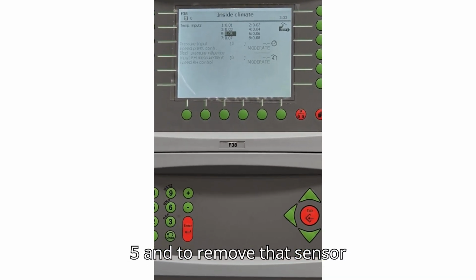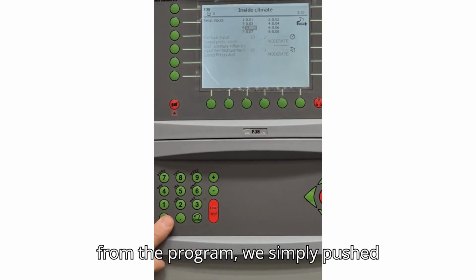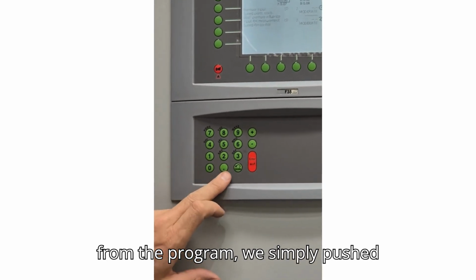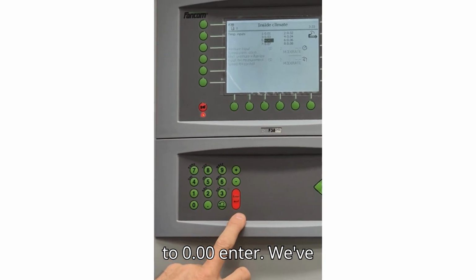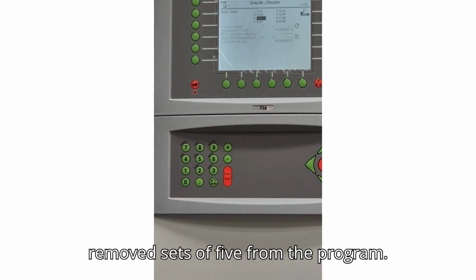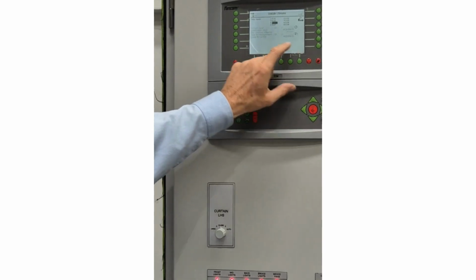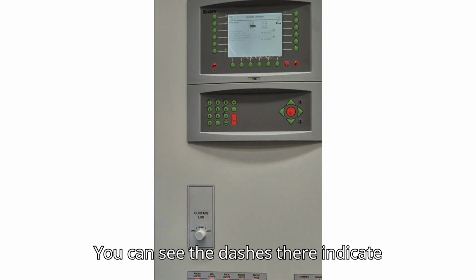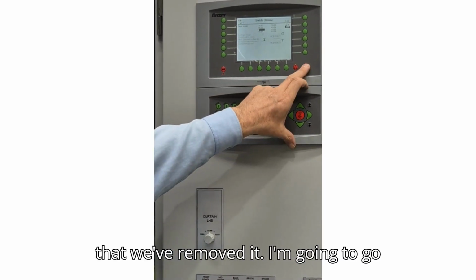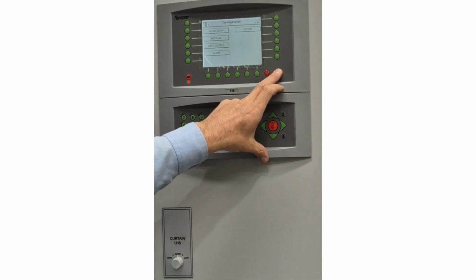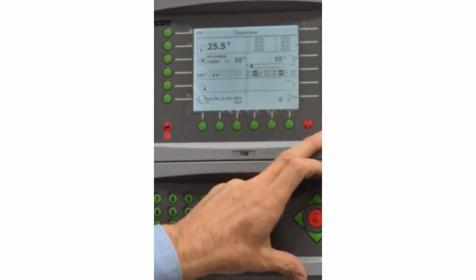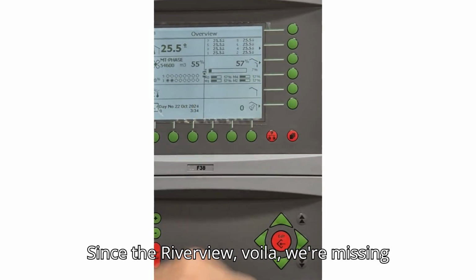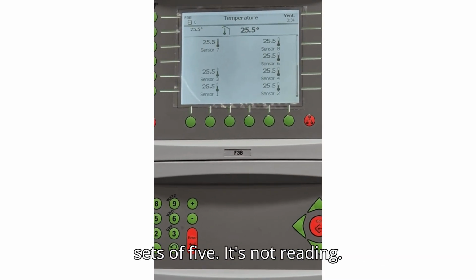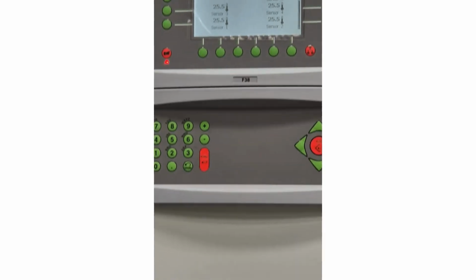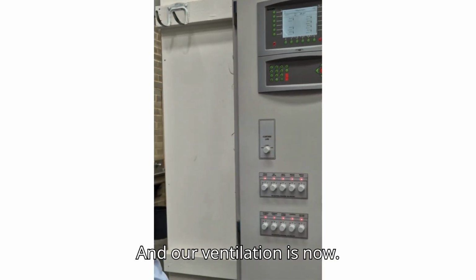And to remove that sensor from the program, we simply push 0.00, enter. We've removed sensor 5 from the program. You can see the dashes there indicate that we've removed it. I'm going to go back to our home screen. Sensor overview, voila. We're missing sensor 5. It's not reading. And our ventilation is now back to normal.